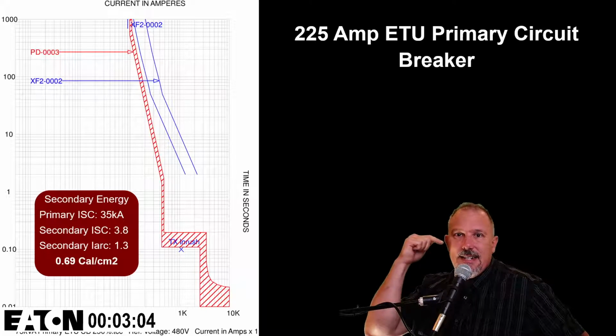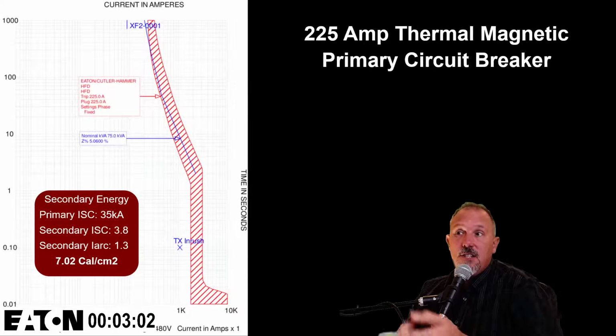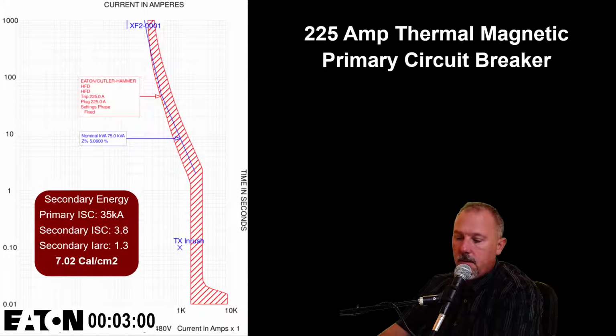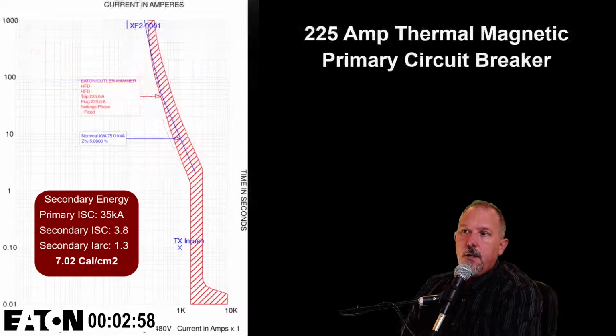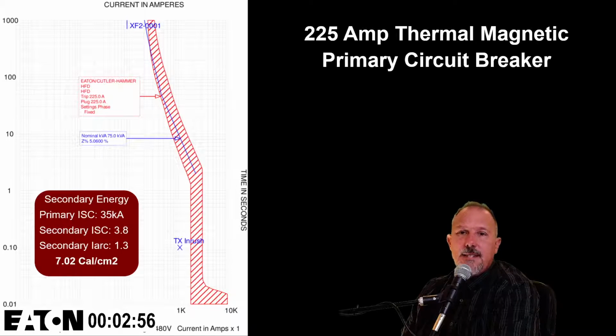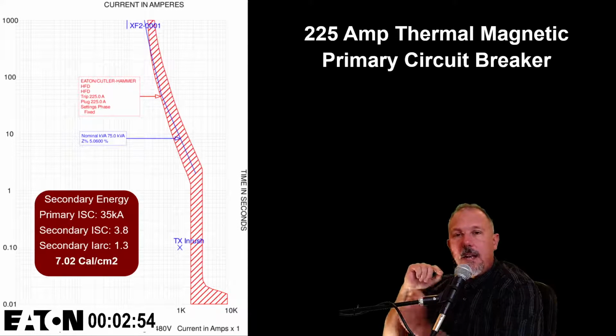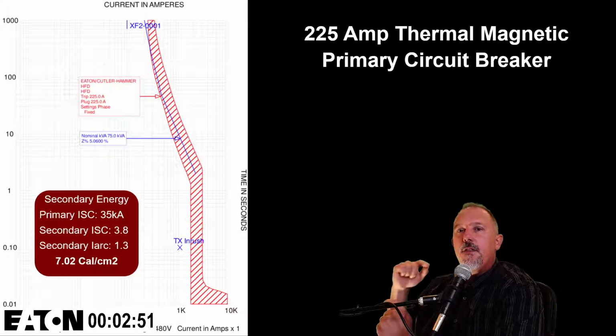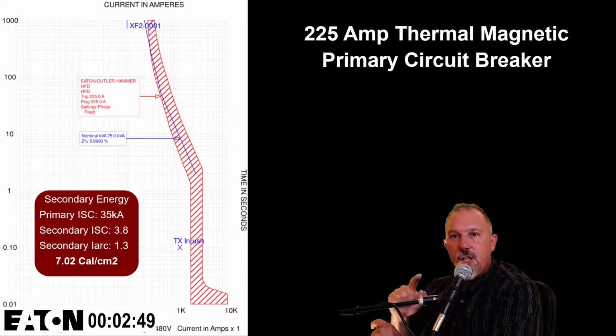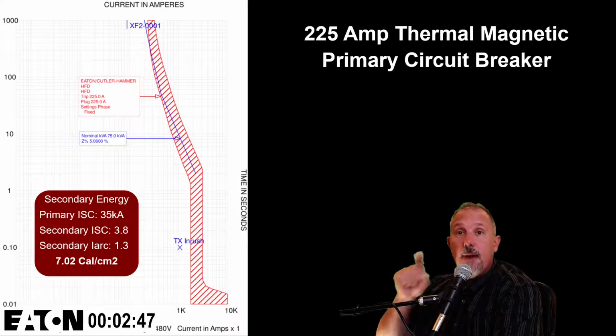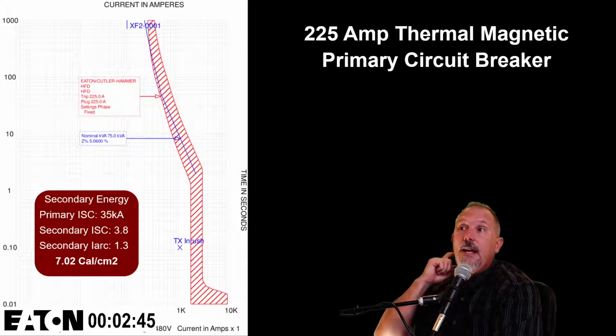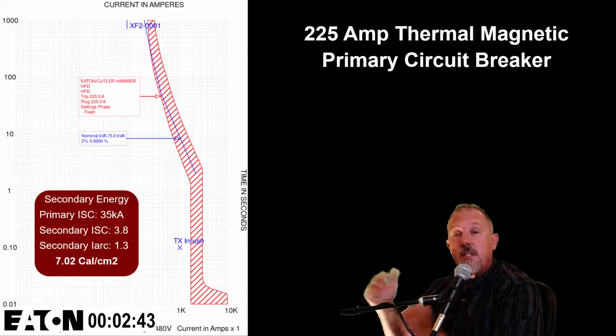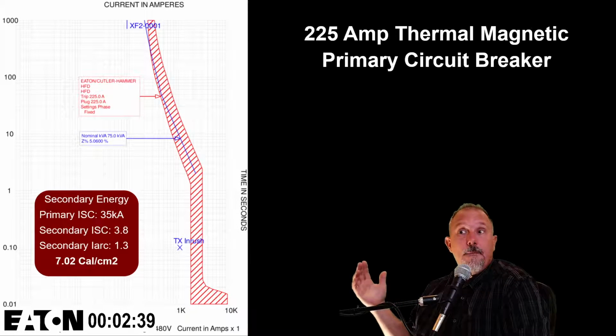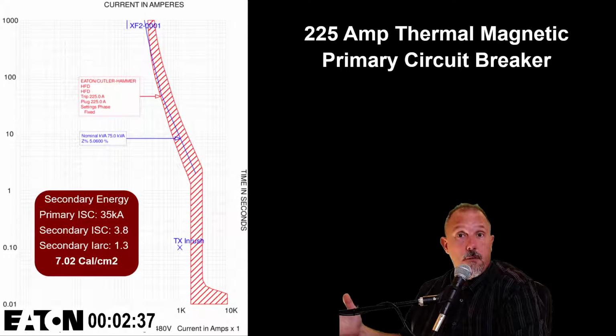And I'll tell you why. You've got to be mindful of the incident energy downstream. I didn't speak to it on this slide, but look at the difference. For the secondary panel board, the incident energy on this transformer is going to be driven by this primary overcurrent protective device, and you've got to be mindful that there is a transformation of currents that goes on, because the transformer doesn't cease to do its job during a fault, right?